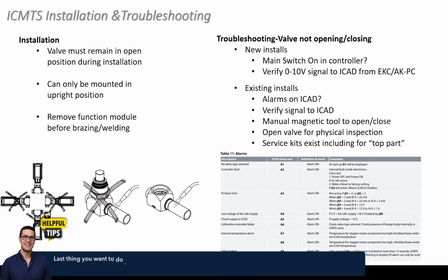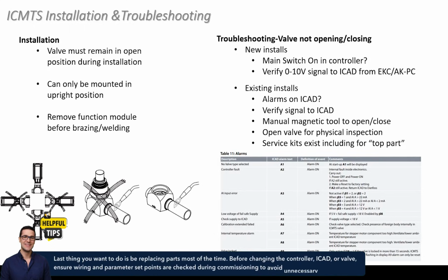The last thing you want to do is be replacing parts. Most of the time, and we'll get into more of it, wiring on at the beginning, and this is usually during commissioning. A lot of the stuff we're talking about, you'll see at commissioning. Wiring, that means switch on, parameter set points, which maybe sometimes you get the system up and running and they're not perfect, but those are the things that you want to look at before you say, okay, let's change the controller, let's change the ICAD, let's change the valve itself.